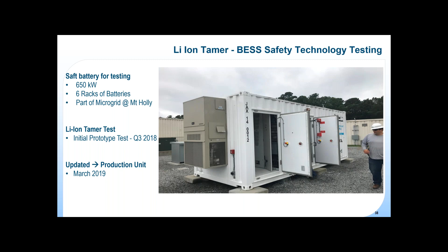The installation of the new Li-ion Tamer technology went extremely fast, using standardized cabling that you can get at any supply store for Ethernet. We were able to take the existing prototype system out and install a production system in its place. That production system is tied into our microgrid controller, sending signals back and forth should we have a problem. Since then, we've standardized on the Li-ion Tamer product as our early detection system deployed on every energy storage project we do at Duke Energy.